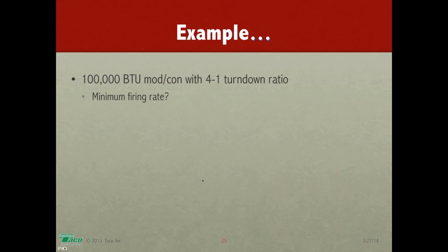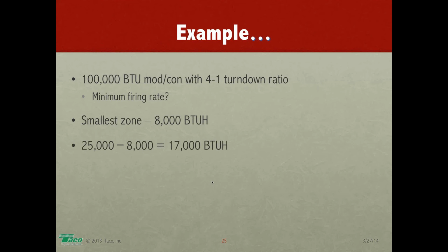Okay, let's do an example. Let's say we have a 100,000 BTU ModCon boiler with a 4-to-1 turn-down ratio. That boiler will have a minimum firing rate of 25,000 BTUs. The load of the smallest zone under design conditions is 8,000 BTUs. To get started, we subtract the BTU load of the smallest zone from the minimum firing rate. So 25,000 minus 8,000 gives us a BTU surplus of 17,000 BTUs.